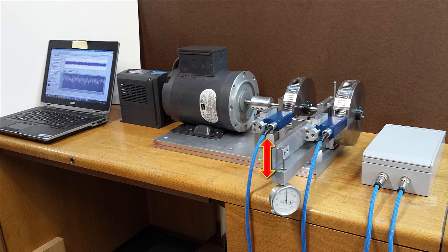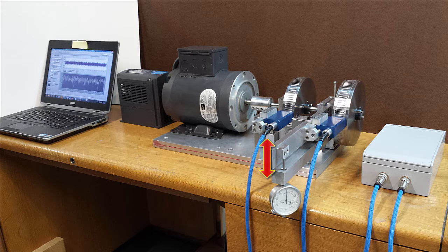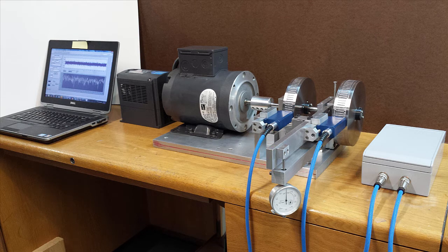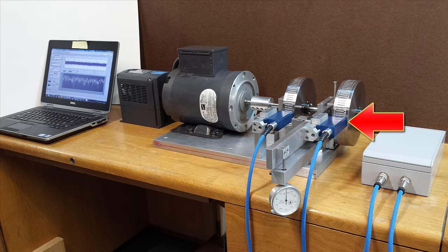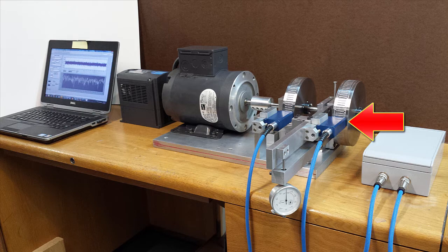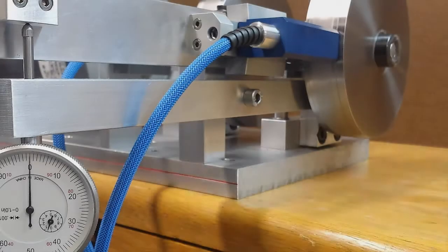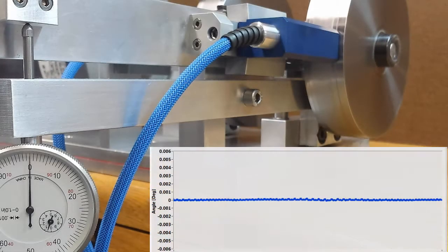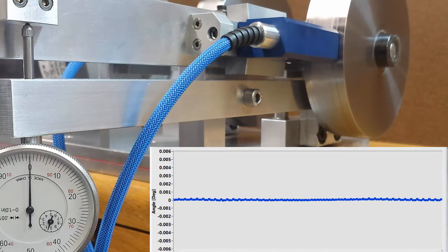The length of the swing arm is 12 inches and the tangential displacement is measured using a dial indicator that has 0.001 inches of divisions. Small tangential movement of the swing arm will change the angular position of sensor number 2 relative to the rotating shaft and the stationary sensor. When movement of the 12 inch swing arm results in 0.005 degree relative rotation.